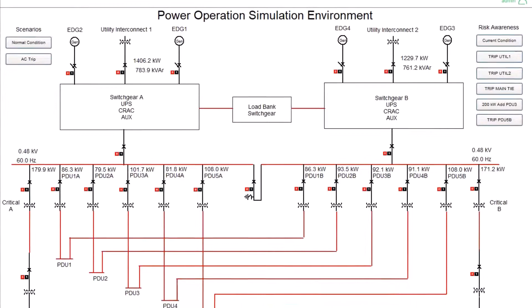In this case, we can see that once the data is brought in from PME, ETAP further expands the visibility of PME by displaying estimated power flow in areas where metering is not available. We can see PME data showing in blue color, and in red color we can see ETAP calculating the power flows across the rest of the model, taking into account the electrical digital twin and the data collected by PME.